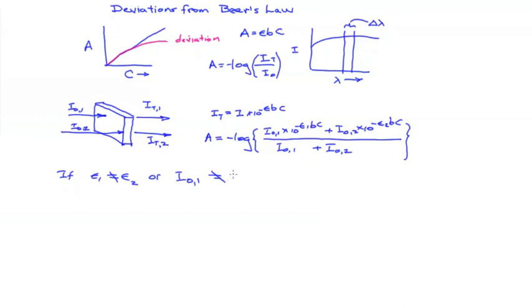The instrument is going to calculate the absorbance from the total transmitted intensity over the total incoming intensity at all the wavelengths. The problem is that this ratio does not converge to the linear relationship between absorbance and concentration. If either the molar absorptivities at the two wavelengths are not equal or the intensities going into the sample at the two wavelengths are not equal then this relationship does not converge or simplify to absorbance equals epsilon bc. And our calibration curve would look something like this.